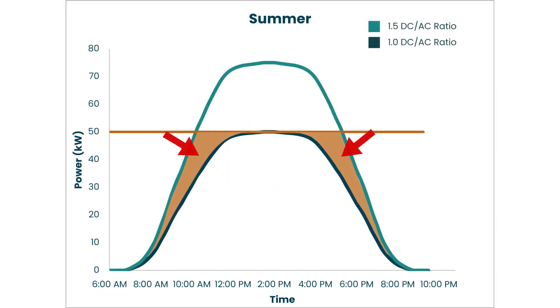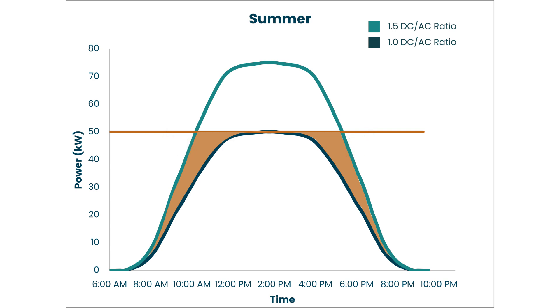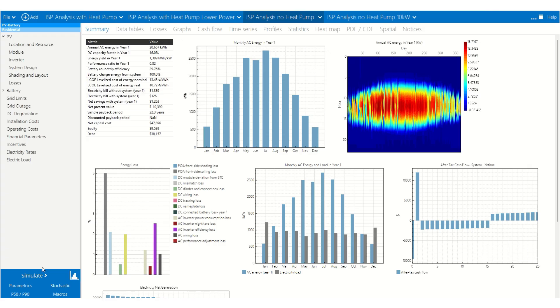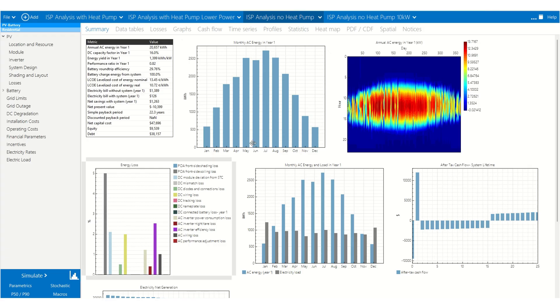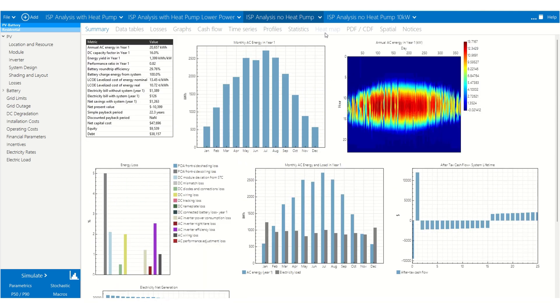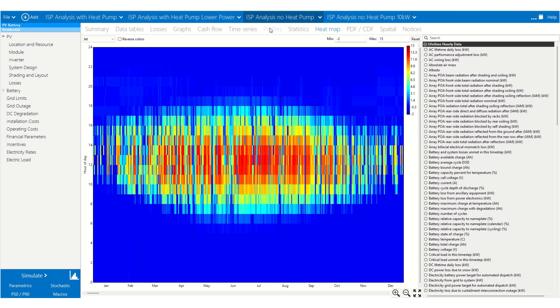Taking a look between summer and winter with a 1.0 and a 1.5 DC to AC ratio, you can see the extra energy you can throughput over the year. Most projects range from 1.2 to 1.4, but finding the right balance is a financial and modeling exercise, and it can really depend on whether it's a residential, commercial, or utility project. If there's energy storage attached to the solar project, the DC to AC ratio can get as high as 2.0 to 2.5.